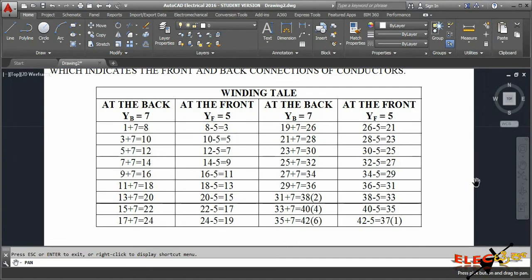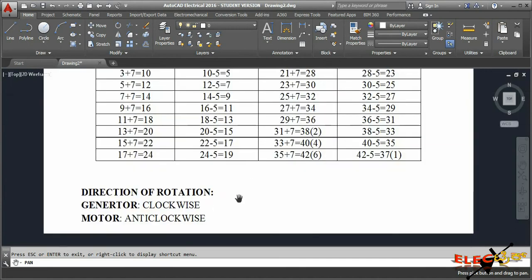In the winding table, at the back with back pitch seven, conductor number one is connected to conductor number eight. At the front, conductor number eight is connected to conductor number three. The direction of rotation for a generator will be clockwise and for a motor will be anti-clockwise, and we need to show the arrow mark direction in the winding diagram.